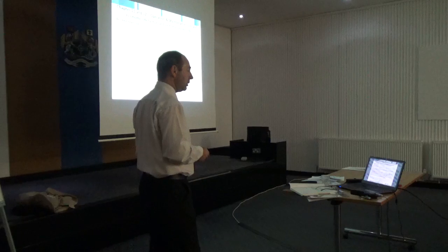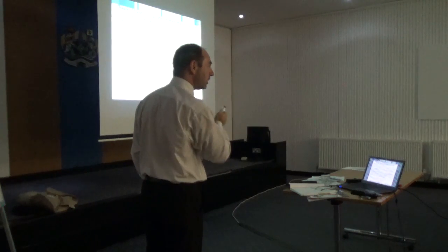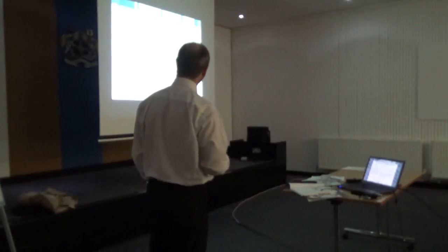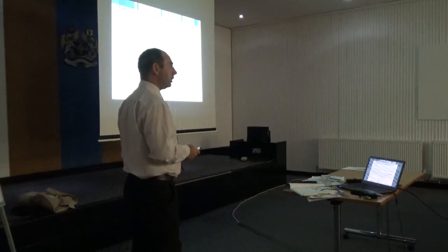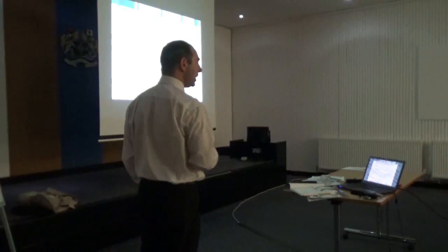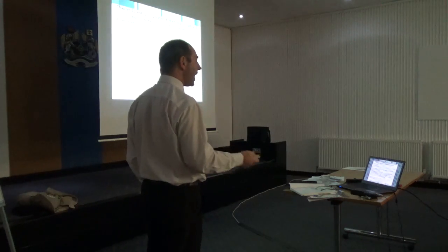So if we apply those variation factors that I touched on a minute ago, as I've done in red there, what we see is that the actual predicted life of that particular asset is no longer 20 years. It's only 16. Now consider, that's been in for 15 years and you're the maintenance man and you've now just had a bit of a wake-up call, because actually you thought you had 5 more years on that asset, but the reality is you've now got 12 months. And that's going to hurt someone, and your finance man isn't going to be very happy because you're about to hit him with a surprise.